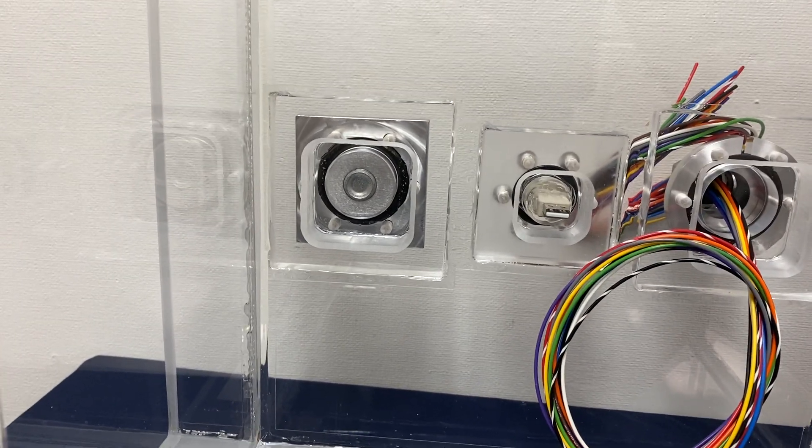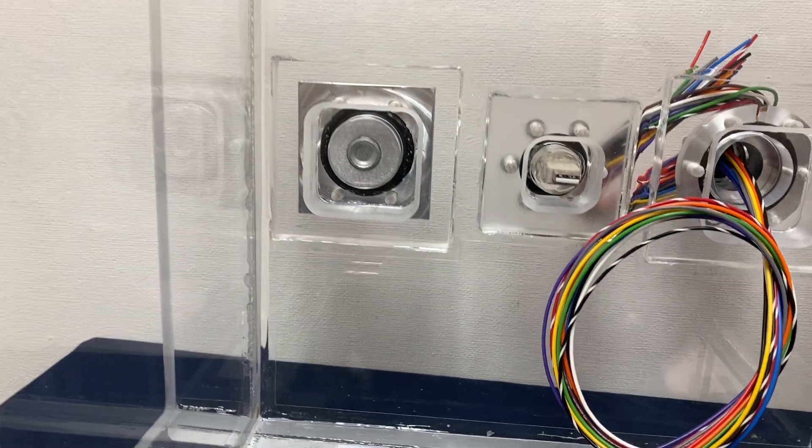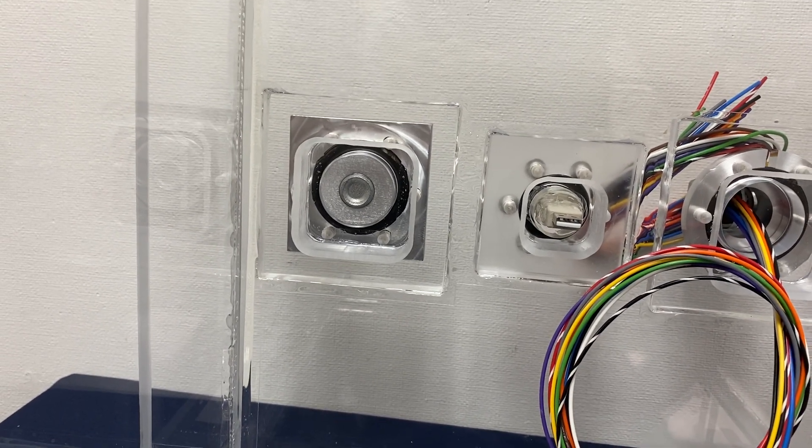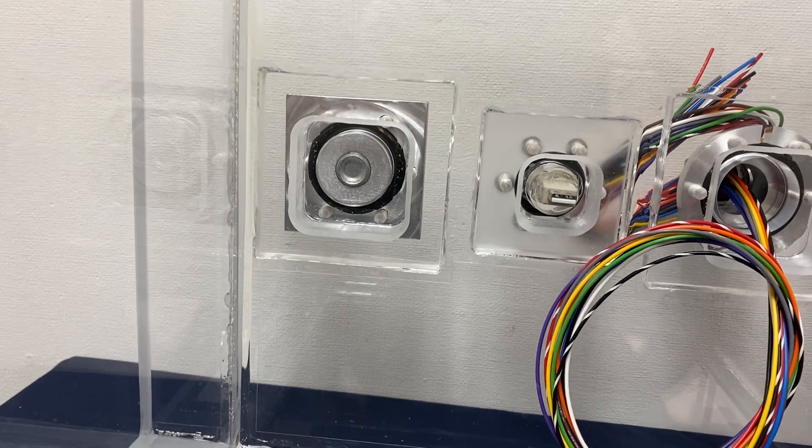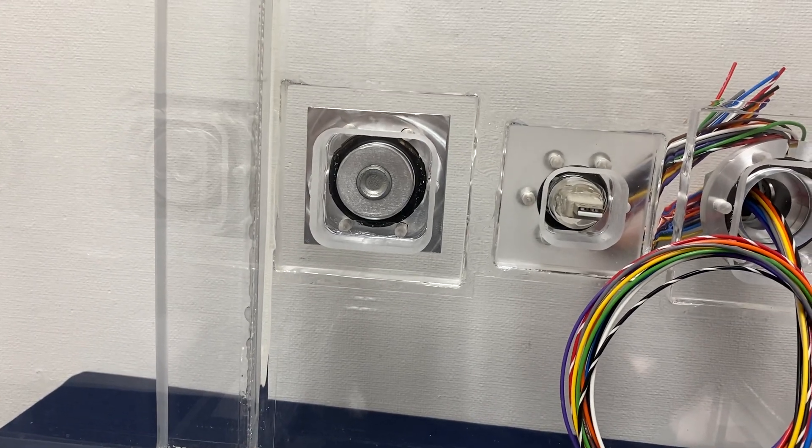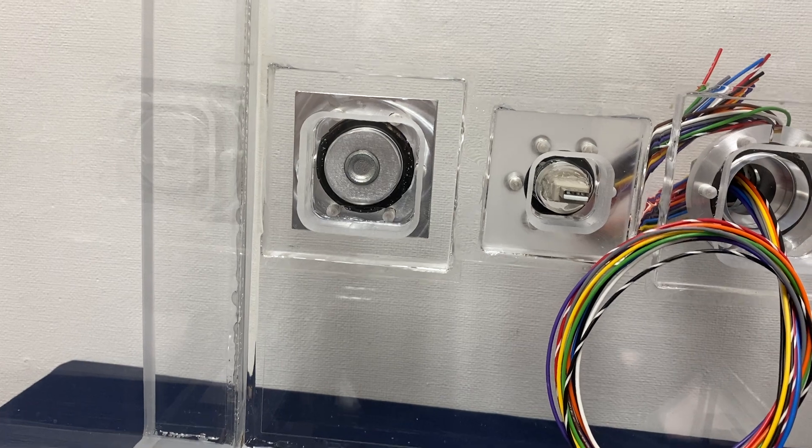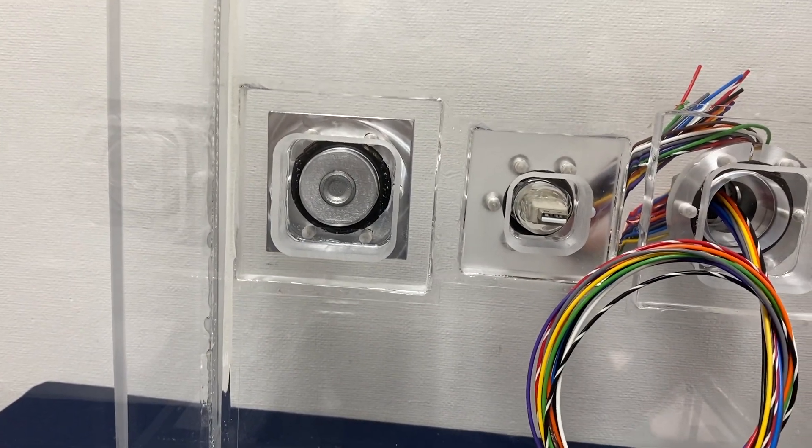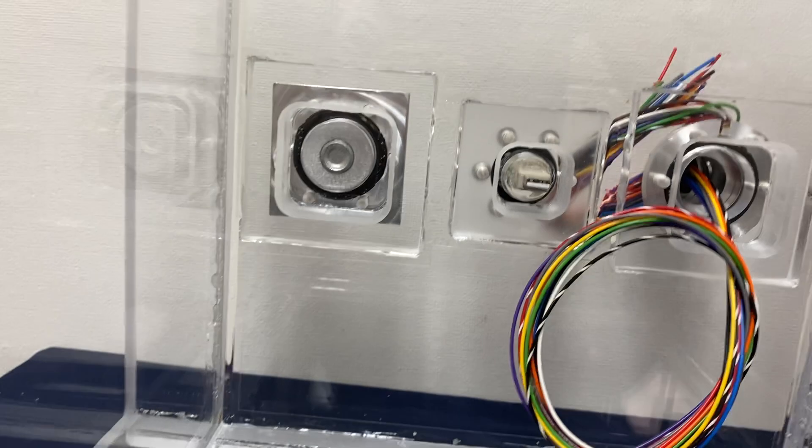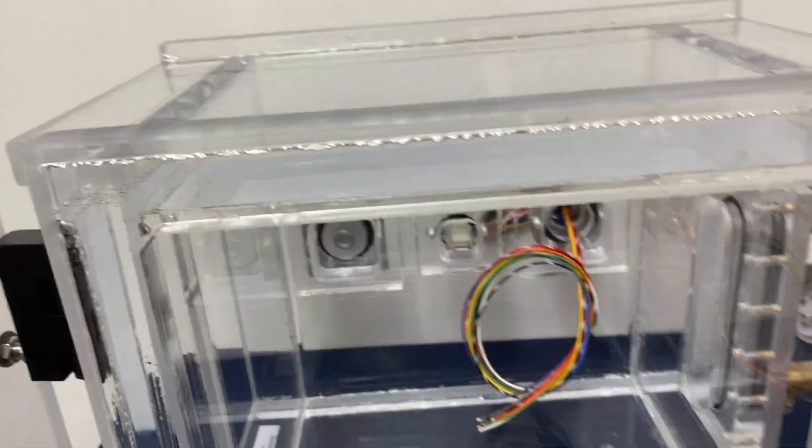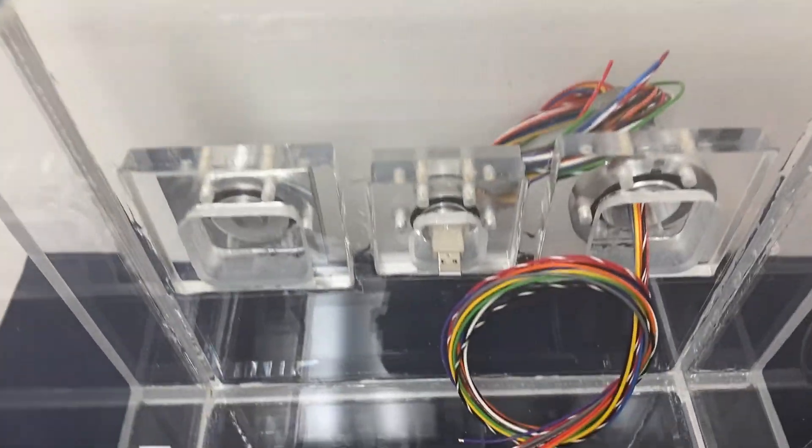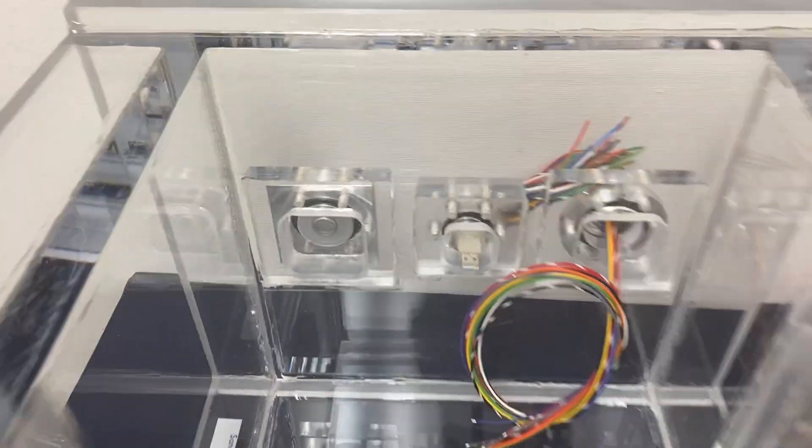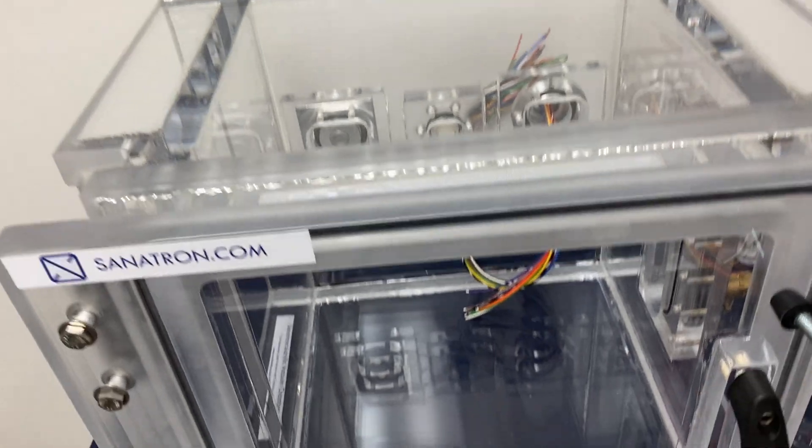This thread is a custom thread—I believe it's like 20 millimeters by one and a half millimeter pitch. And our customer will take their vacuum feed-through and they will connect it to this thread, and then they can connect their probe into this acrylic vacuum chamber and perform their test. So as you can see, all three vacuum feed-throughs are placed on the rear wall.